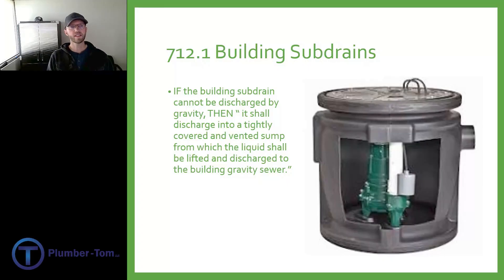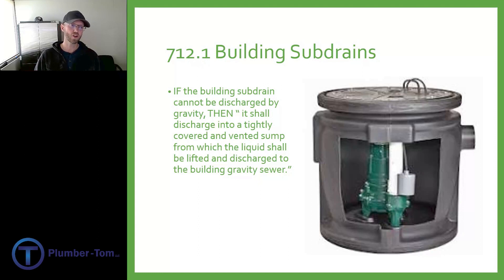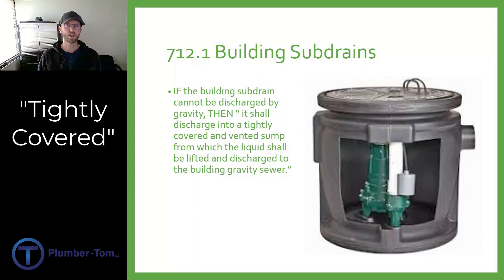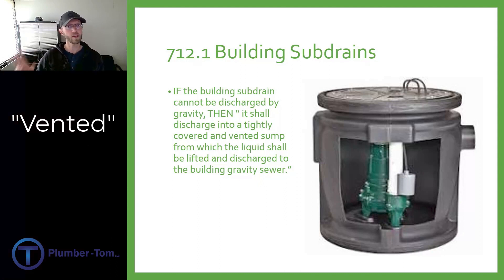712.1 says that if we're going to put in one of these building sub-drains draining into a tank, it shall discharge into a tightly covered and vented sump from which the liquid shall be lifted and discharged to the building gravity drain. Key words: tightly covered — you do not want sewer gas getting out into the building — and vented, because when you turn on a pump and push out all that liquid, that volume has to be replaced by air, and without a vent these will fail.